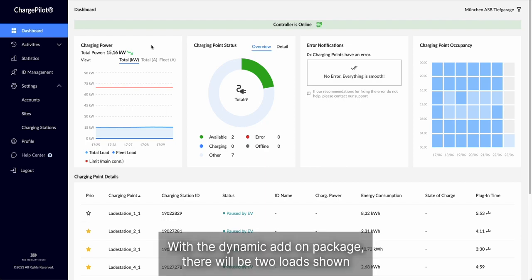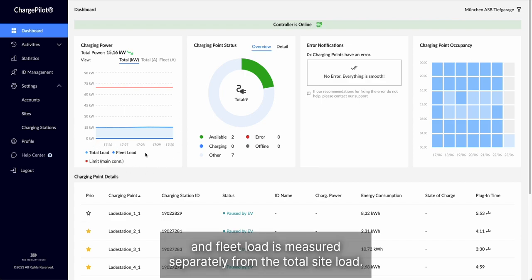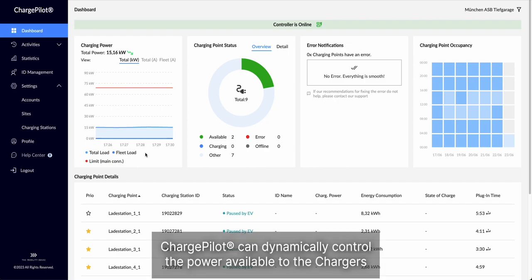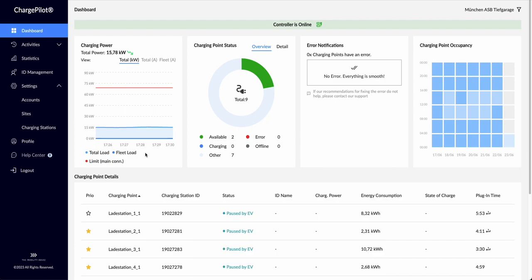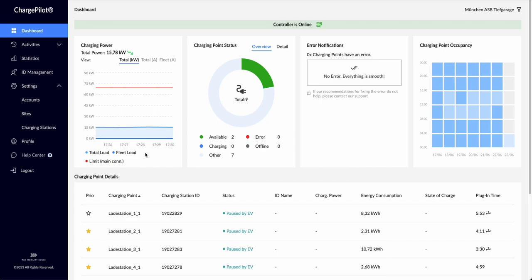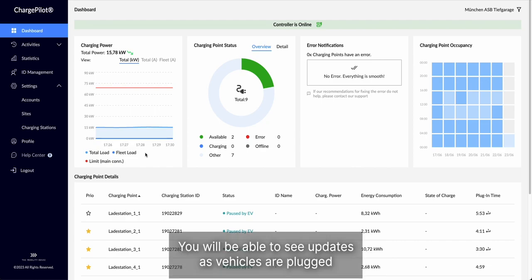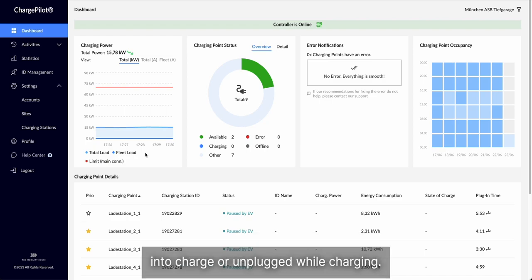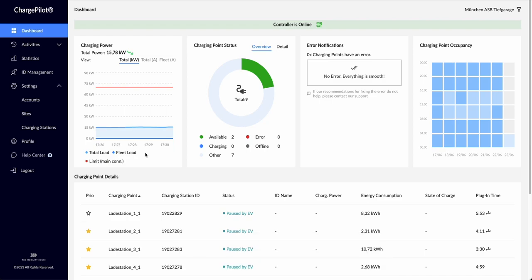With the dynamic add-on package, there will be 2 loads shown, and fleet load is measured separately from the total site load. ChargePilot can dynamically control the power available to the chargers based on the site's other power draws in real time. You will be able to see updates as vehicles are plugged into charge or unplugged while charging.